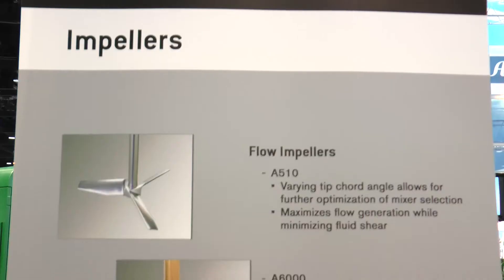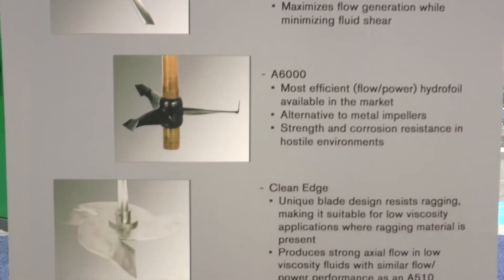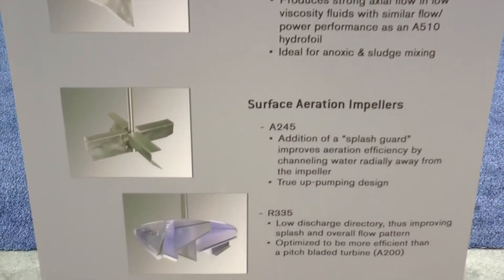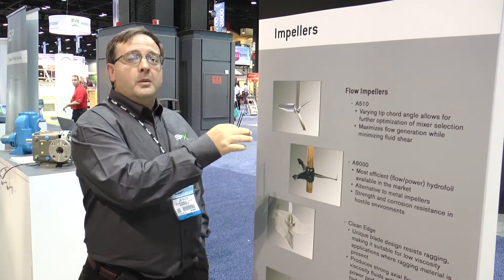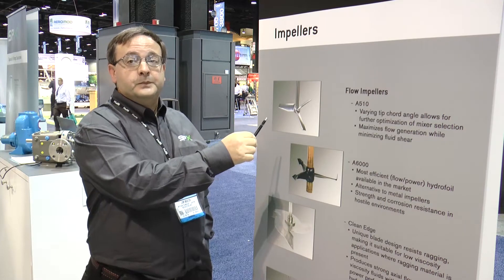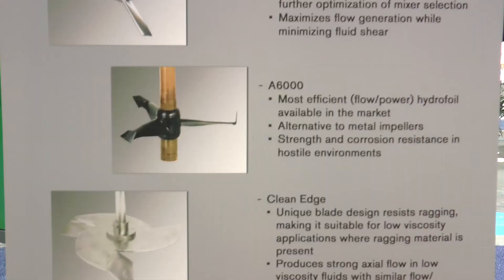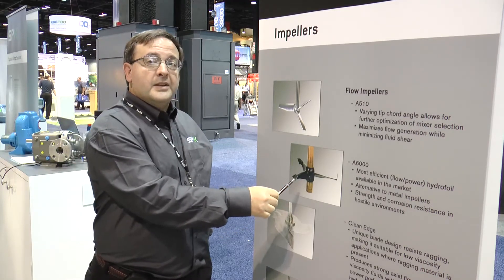Lightnin's most significant contribution to the mixing market is our impeller technology. We revolutionized the industry a number of years ago by introducing the high efficiency axial flow impeller. This replaced older type impellers for mild blending and solid suspension applications and introduced a power reduction of about 40%. In addition to that, we then introduced a composite style impeller, which further helped reduce the sizing of gearboxes and shaft design through our lower weight composite material.